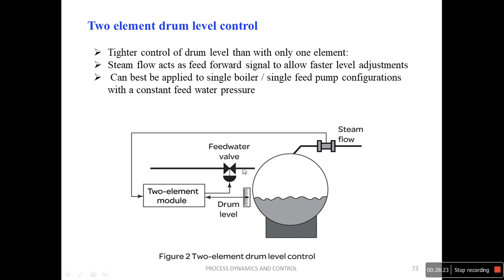So for that, just like a feed forward control, we have to consider the steam flow also as another disturbance variable. Here I am going to consider two variables, that is two elements: drum level as well as steam flow. That's what is called a 2 element drum level control. Here the steam flow acts as a feed forward signal to allow faster level adjustments. It is applied to a single boiler or single feed pump configuration with a constant feed water pressure. For the controller, we take the information from the drum level as well as steam flow. There is a desired level, and depending upon this, we change the feed water flow rate. So that disadvantage can be eliminated.